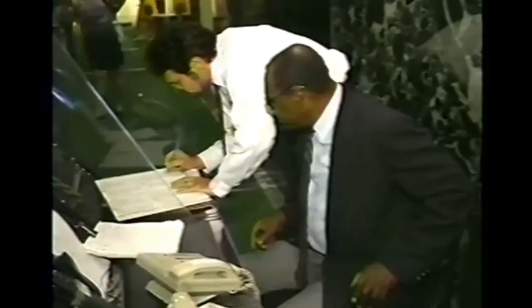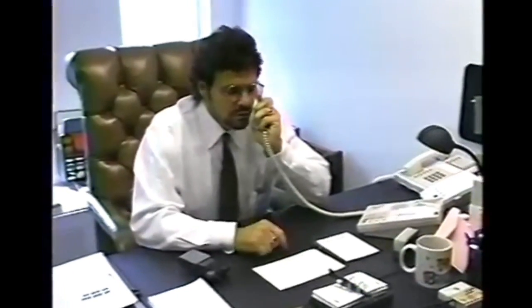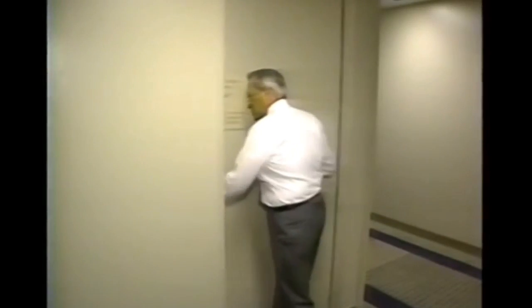If you are the floor warden or acting floor warden, you may start your day by signing in at the desk of the Deputy Fire Safety Director who is responsible for your floor. Later, you report by telephone on members of your floor team who are absent that day and give the names of people who are substituting. You also report on your periodic check of stairway doors and make certain none are obstructed, inoperable, or locked. And you report if you have seen trash on the stairwells or in the freight elevator lobby. Trash is an obvious fire menace.